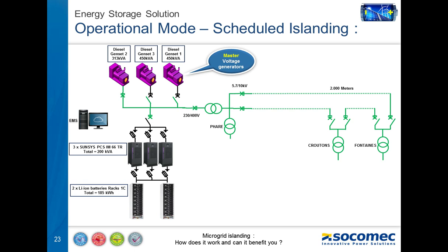In this first step of this project, even if the SUNSYS PCS are able to manage alone the black start and the grid forming functionality, it has been decided to let the control of the microgrid to the genset when these ones are in parallel with the energy storage system. In this situation, the genset supplies the microgrid as a master voltage generator, taking care of the voltage and frequency regulation. This is a really specific application for the Island project. In most of our applications, the energy storage is the master of the microgrid, and the genset are only present as a reserve of energy in case of need.